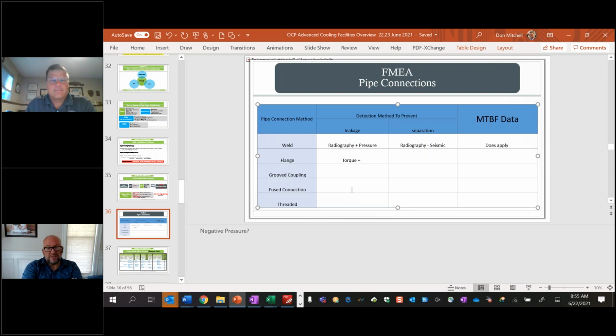And I'll also add one last one, which is something I've used in the past, and you also might see if you hire a contractor to come in and do some of your piping for you. These are not crimped connections in the normal sense of a swage, like you would use on a high pressure system, like hydraulic fluid, but low pressure compression systems. Viega comes to mind as one. These are where you go around your copper or a stainless pipe with a set of crimps, and it crushes the housing around an O-ring or some other kind of a sealing mechanism. But I think they should be included, and we should at least weigh in on them so that users can get a feel for what this group and the expertise here thinks about them.